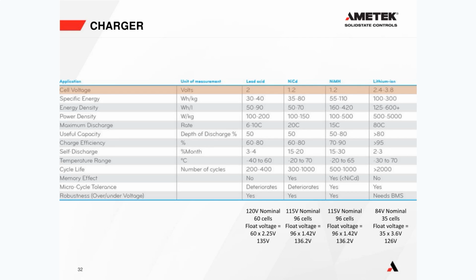For NiCad cells, you're usually going to have 96 cells, sometimes 92 cells, depending on the engineer who designed the system and the parameters. A NiCad cell usually gets charged, if it's a single stage charge level, at around 1.42 volts per cell. That makes a total output voltage of 96 cells times 1.42 volts, equal to 136.2 volts. So you can see there is a 1.2 volt difference between the float voltage for a 60 cell lead acid battery and a 96 cell NiCad.